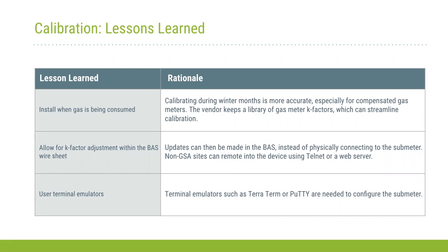So allowing K-factor adjustment in the BAS was also a best practice, and Bill set that up for us. That was because you can remote into this device if it's not in a GSA setting, but that portion had to be disabled. And so we couldn't use Telnet or web server in our application. If it's a non-governmental application, you may be able to use that depending on your security requirements of your business, but we weren't able to. And so we had a workaround where we allowed for adjustment of K-factor in the BAS before it produced a result that we trended.